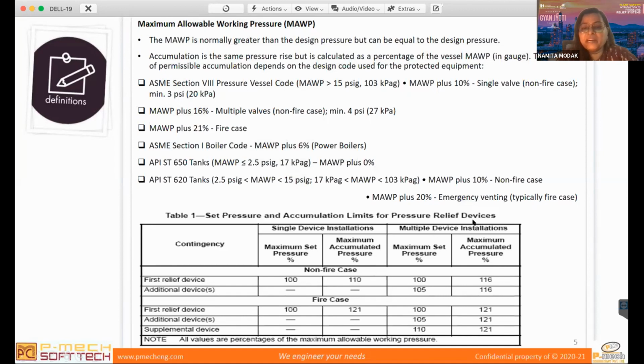Okay. So if I have multiple PSVs, let's say I have 2 PSVs, my first PSV set pressure will be 100%, which is 10 bar gauge, and my additional PSV is set at 105% of 10 bar gauge. In that case, my relieving pressure will be more than my single PSV case. For the single PSV case, it's 110%, but for my multiple device installation, it will be 116%. Now talking about the fire case, whether it's a single PSV or multiple PSVs, your relieving pressure will be 121%, and your set pressure follows the same criteria as the non-fire case. And here another third PSV has also been given. The set pressure of the third PSV will be 110% in this case.